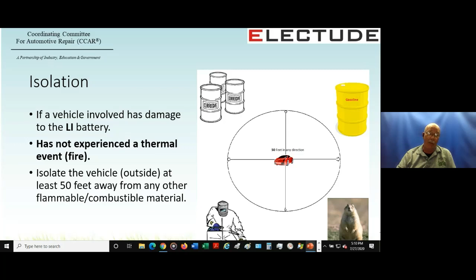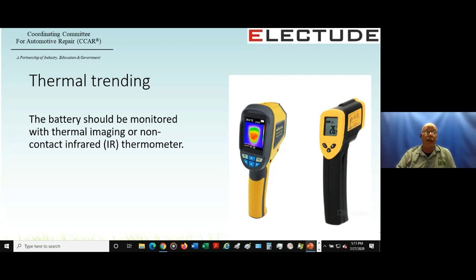The battery should be monitored with thermal imaging equipment or a non-contact infrared thermometer for a sufficient period to determine if the battery is getting warmer or cooler over time. Once it's been determined that the battery temperature is trending at a stable ambient, or is actually cooler than ambient, it's possible to address further repair operations. Getting warmer above ambient, and that is possible, is not a good thing.